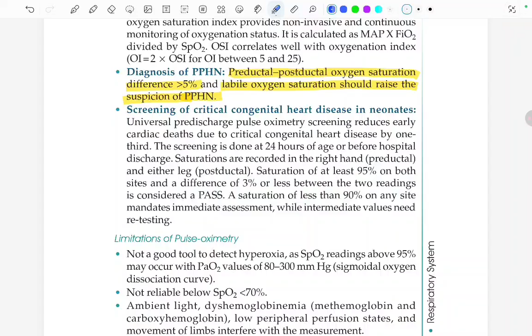Now, what are the limitations of pulse oximetry? It is not a good tool to detect hyperoxia, as an SpO2 reading above 95% may occur with PaO2 values of 80 to 300 mm of Hg, due to the sigmoidal oxygen dissociation curve. It is not reliable below SpO2 of 70%. Ambient light, dyshemoglobinemia, methemoglobin, and carboxyhemoglobin, low peripheral perfusion states, and movement of the limbs interfere with the measurement.